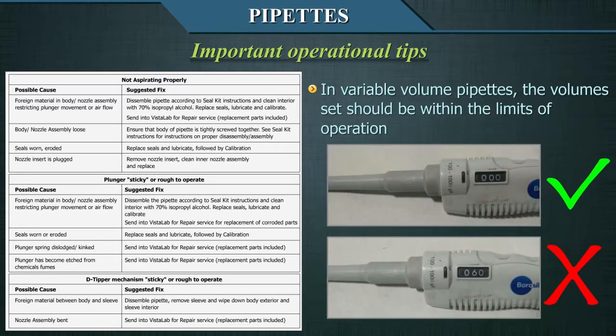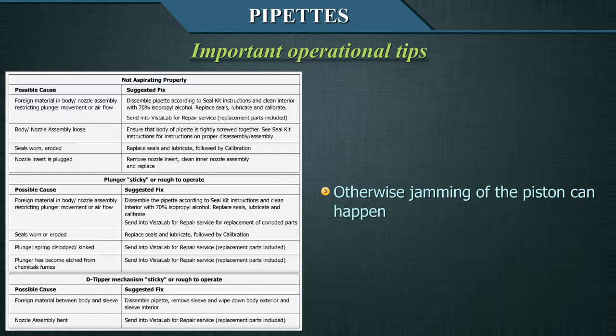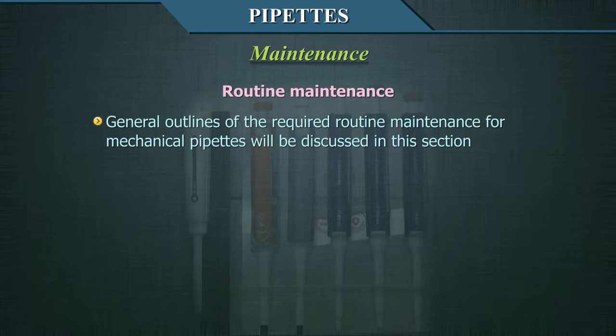In variable volume pipettes, the volume set should be within the limits of operation; otherwise, jamming of the piston can occur.